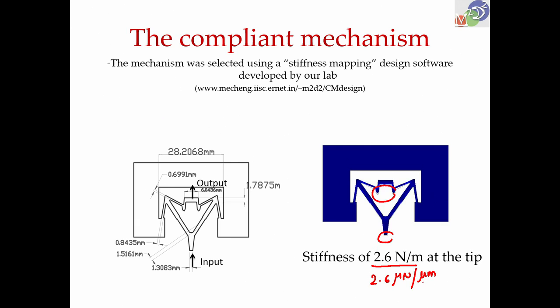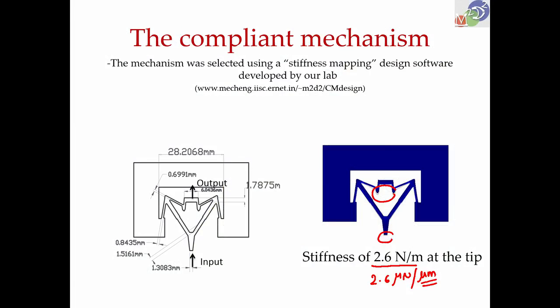So, stiffness has to be in that range. Micrometer displacement is amenable to measuring using visual techniques, just optical microscopy. You do not need to go beyond that. So, we can go for an off-the-shelf digital microscope and measure this very small displacement. So, that was the principle. Look at the size of it: this length from here to here is 28 millimeters, and it is not that small, in fact it does not need to be. Even the narrowest beam, which is over here, is 0.7 millimeters, so 700 microns. You do not need microfabrication to make this. I will tell you how we did it. We can design these things to have the stiffness that we want, so that small forces applied over here will cause measurable displacements using a digital microscope.